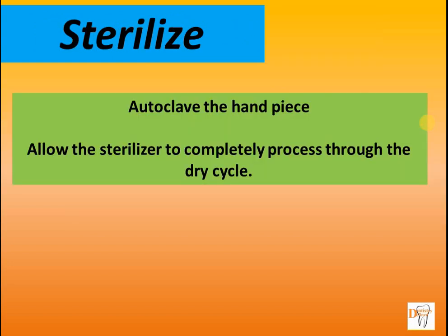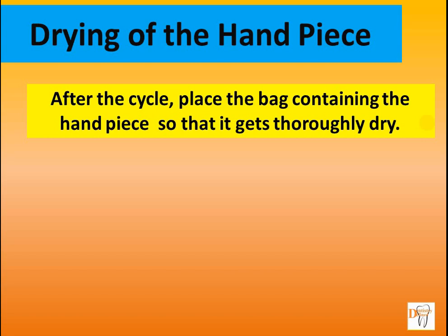Coming on to sterilization. Autoclave the handpiece following manufacturer guidelines. Allow the sterilizer to completely process through the dry cycle. Drying of the handpiece. After the cycle, place the bag containing the handpiece so that it gets thoroughly dry. If you are using a combination of paper and plastic bag, the paper side should be on top of the sterilizer to thoroughly dry. This is a warm area. As the heat from the sterilizer rises, the handpiece will dry more thoroughly.